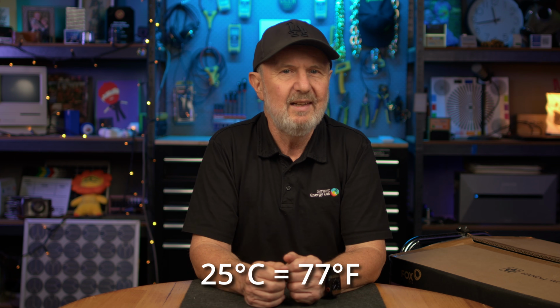From the master unit, which sits on top, you're going to have some cables that go off to your inverter, and those cables don't need to be massive because they're running at high voltage and therefore low current. The round trip efficiency is very good - greater than 95% for the round trip on this battery pack when tested at 25 degrees Celsius test conditions. Not sure what that is in Fahrenheit - I'll put it in the description.